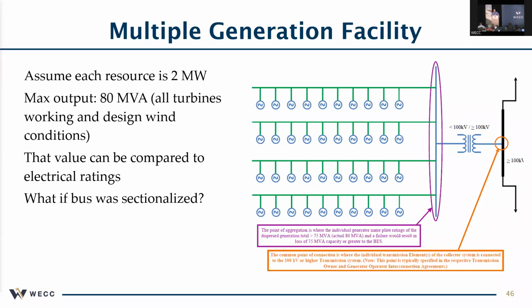You're still looking at the connection point there, but if that bus were sectionalized, it's possible. And this is where we see sometimes it might not be able to carry all of the current from one of those strings or two of those strings. So that's something that every time there's a circuit breaker sectionalizing device, it's good to assess that on its own and see how it impacts the overall facility for these collector facilities.